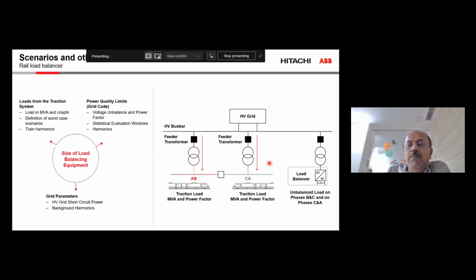So this is just a demonstration of what I am showing here. Before getting into this network, the size of the load balancer we need, to compensate for both real power unbalance and reactive power compensation, depends on the load MVA consumed by the railway network, and the train harmonics, whether lower order or higher order, which we should be aware of. Then there is the worst case scenario we expect in terms of reactive power compensation required, that is power factor compensation, and the unbalance we accept as a worst case.